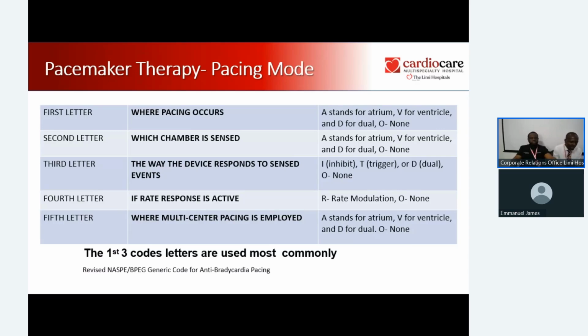So let's go with an acronym, VVI. That's very basic. VVI means that I want to pace in the ventricle, the first V. The second V, you want to sense in the ventricle. Then the third letter, an I, in this case means inhibit. Meaning that if you see something in the ventricle, do not carry on with your first objective, which is to pace. If you do not see anything, then go ahead and pace. So it's like yes or no. If it's there, don't do that. If there's a QRS, don't pace. If there's no QRS, pace.